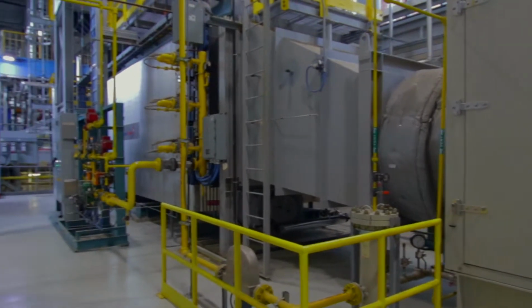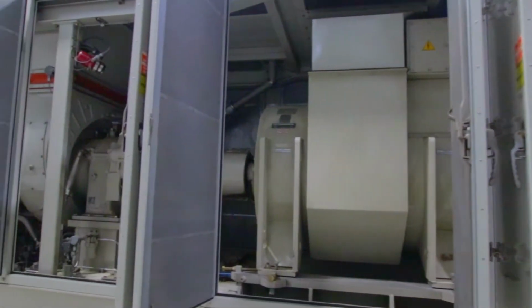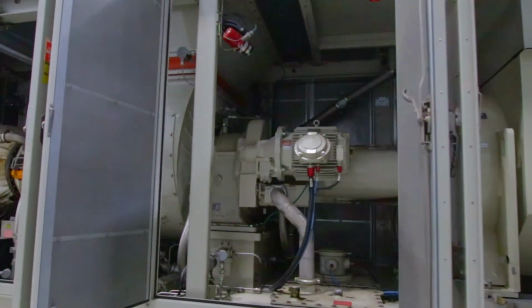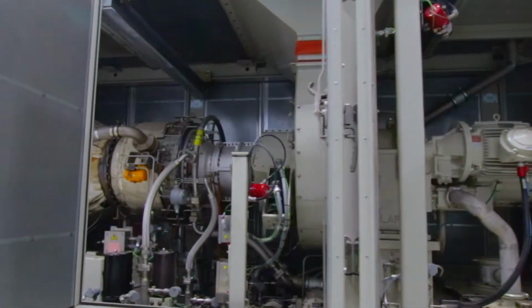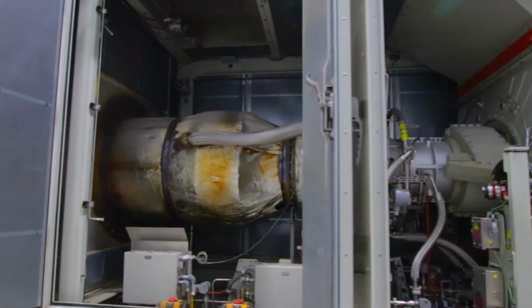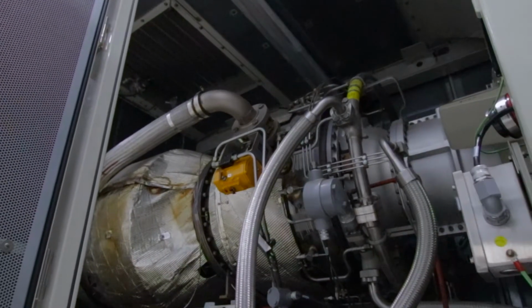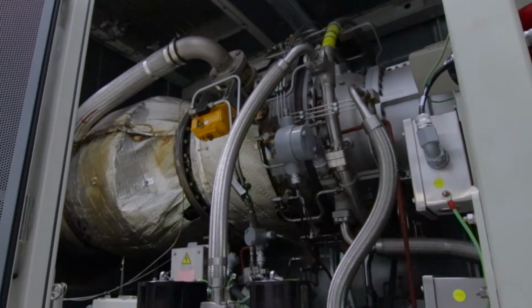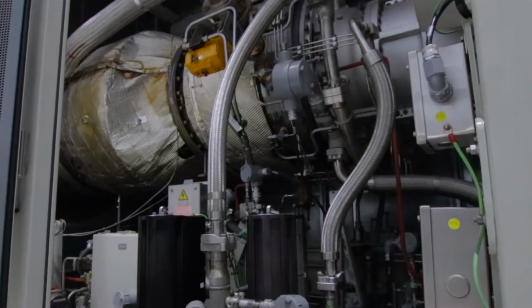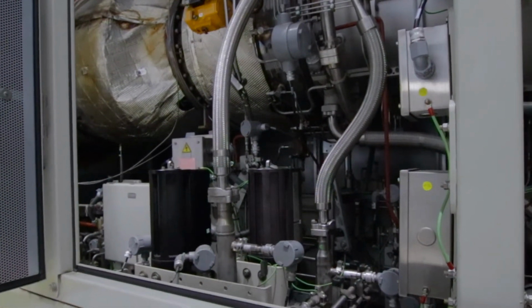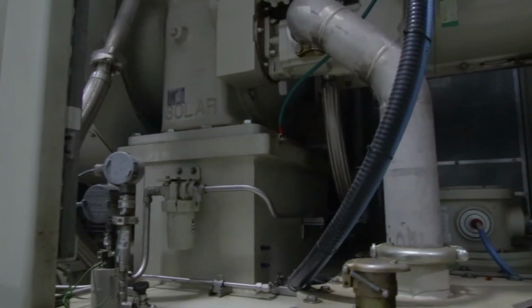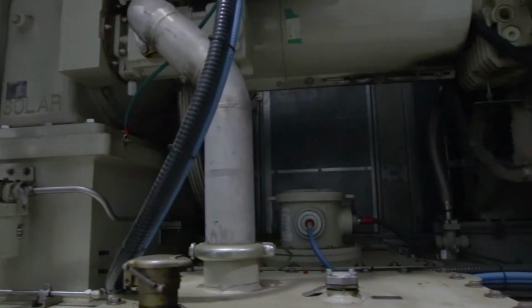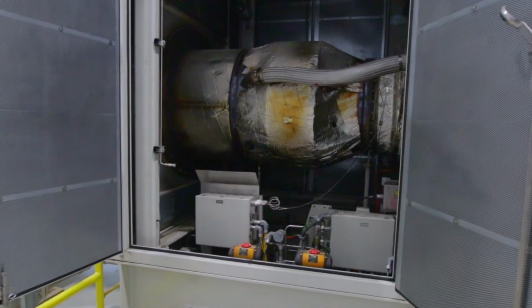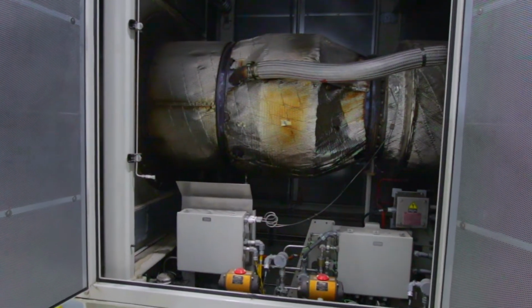So in this case, the industrial gas turbine works basically on sucking in a whole bunch of air. So it pulls in a big amount of air. That air is then compressed in the compressor section of the turbine. Then it makes its way into the combustion section where fuel is added and we have a combustion process. And then as a result, that gas is expanded across the power turbine, and that's what makes the electricity, and then the exhaust gas goes to the heat recovery steam generator. So you're sucking in a lot of air, you're burning fuel and you're heating up that air, and the expansion drives the energy generation.